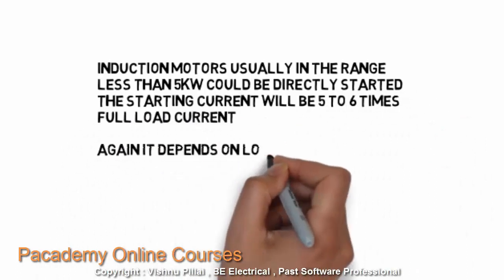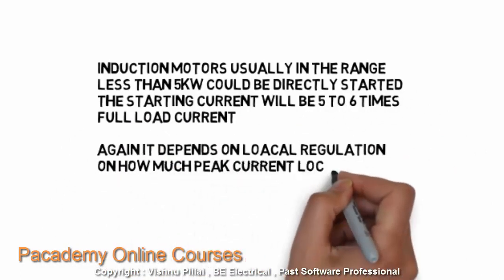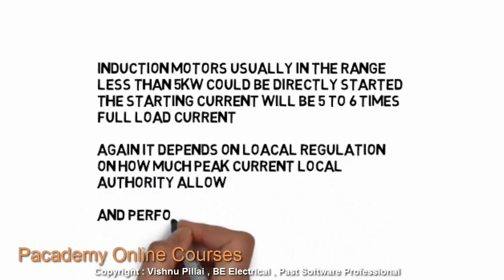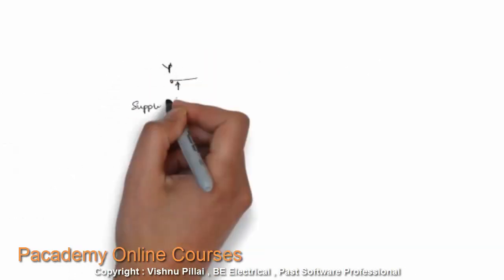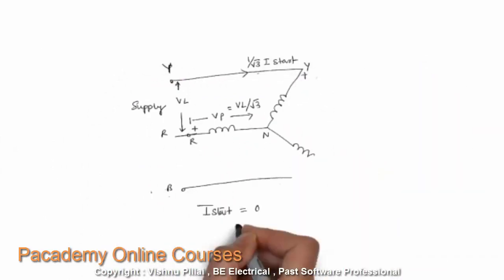Induction motors in the range of less than 5 kilowatts can usually be started directly online, and the starting current will be 5 to 6 times the full load current. It depends on local regulations regarding how much peak current the local authority allows, and on the motor's performance specifications supplied by the manufacturer. Based on that, you can decide if you can start your motor — usually up to 5 kW and sometimes even 10 kW — directly online without damage.